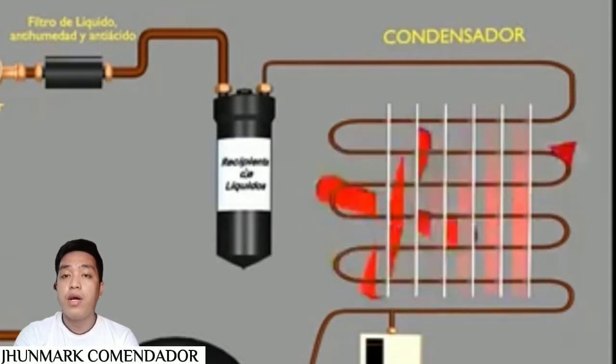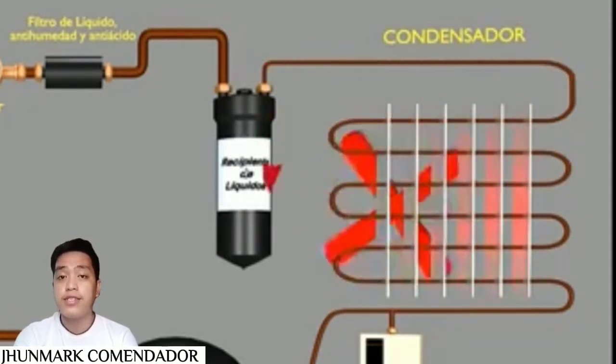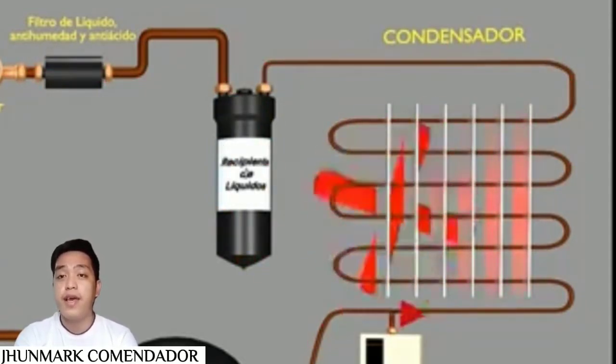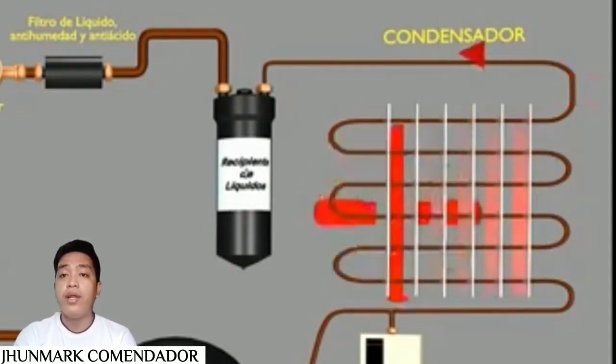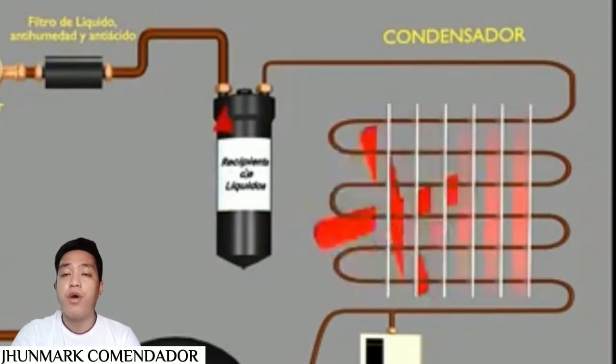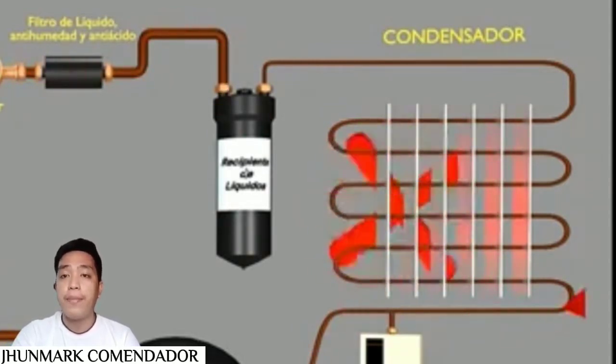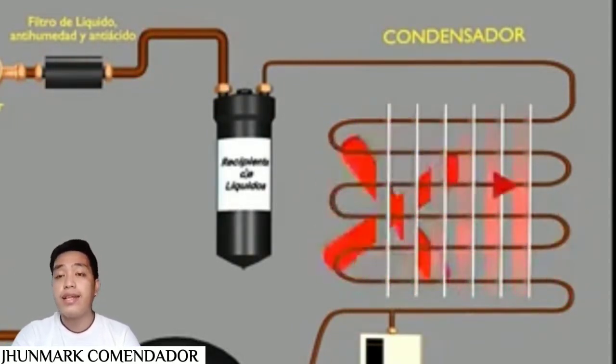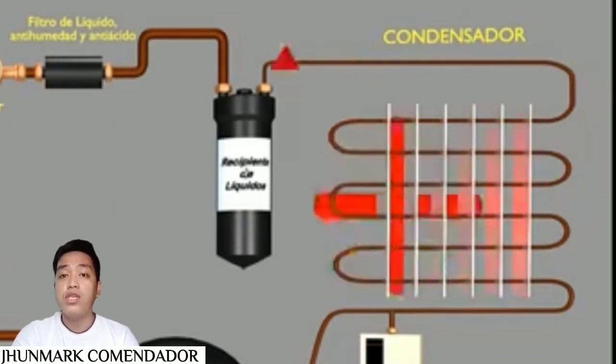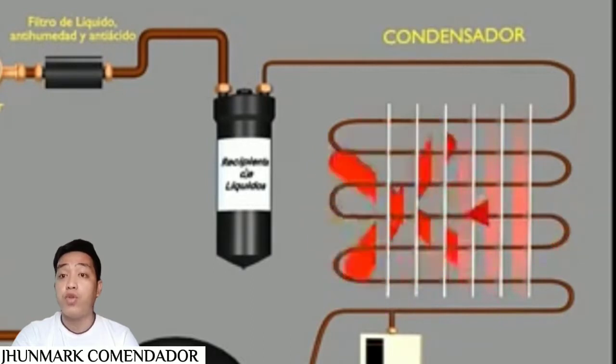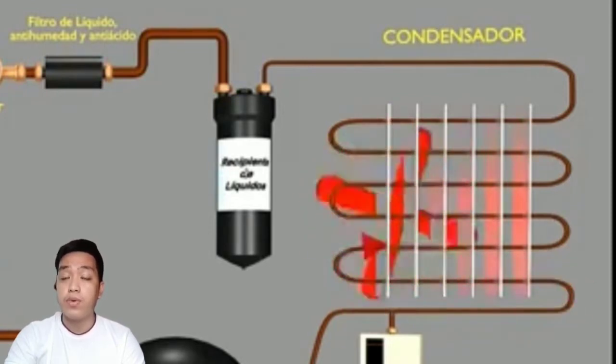First is the desuperheating phase, the second is the condensing phase, and the subcooling phase is the last. In this phase, the change of state of our refrigerant happens from vapor to liquid inside the condenser. It will desuperheat by removing the sensible temperature, approaching the condensing temperature, and this is where the change of state happens before it subcools.